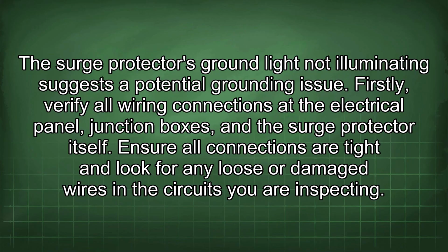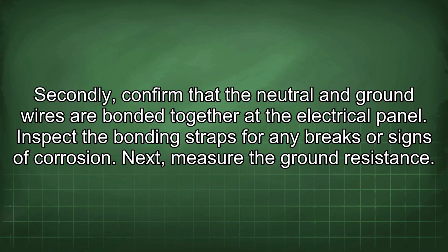The surge protector's ground light not illuminating suggests a potential grounding issue. Firstly, verify all wiring connections at the electrical panel, junction boxes, and the surge protector itself. Ensure all connections are tight and look for any loose or damaged wires in the circuits you are inspecting. Secondly, confirm that the neutral and ground wires are bonded together at the electrical panel. Inspect the bonding straps for any breaks or signs of corrosion.